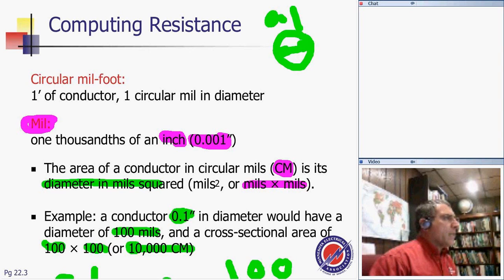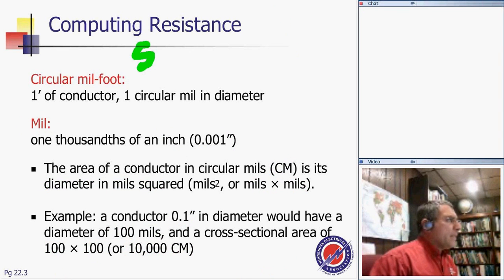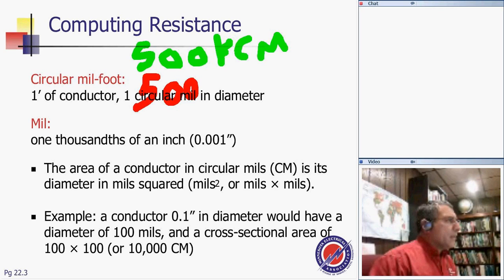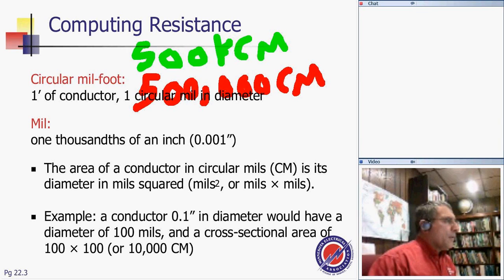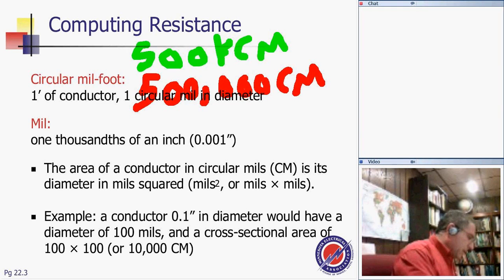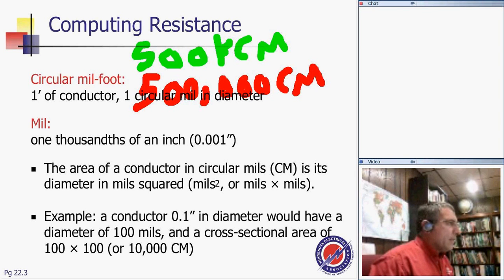Here's what we care about. When I say a 500 kcmil, remember the 500 kcmil, that's a very common one. This means it's 500,000 circular mils. If you want to find in mils the cross-section area for this, take the square root of this. You take 500,000, and take the square root of this. You get about 707.